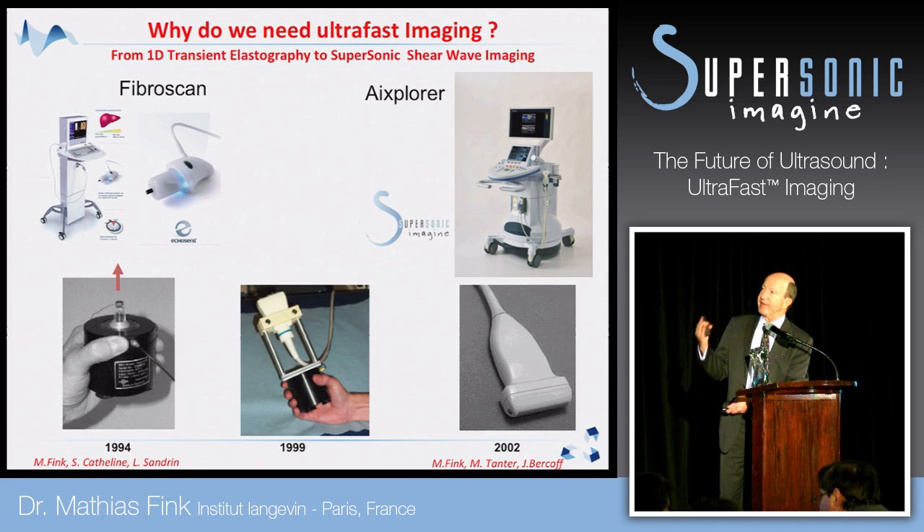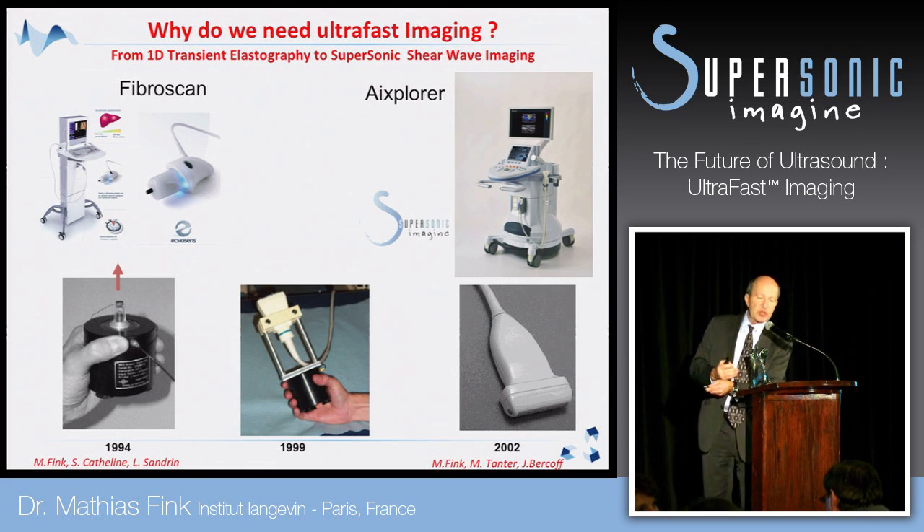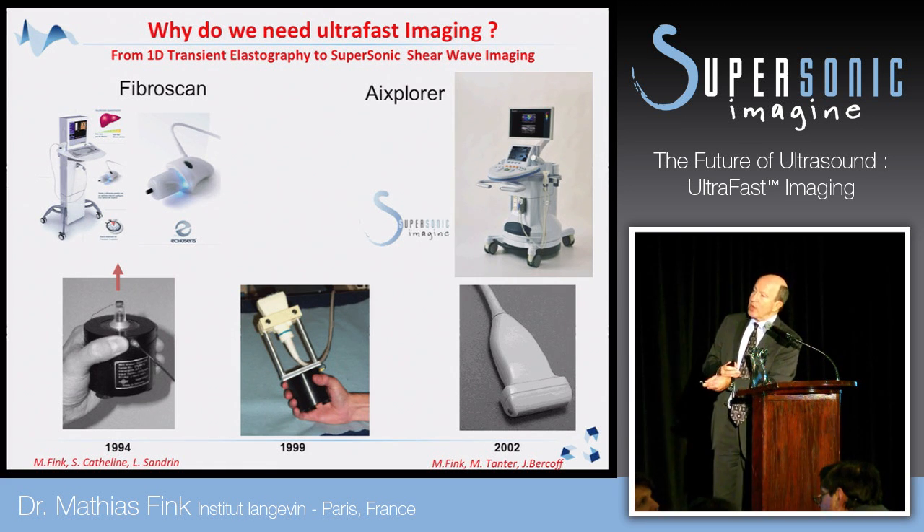In our lab in 1994 I had the idea to make a system to measure the elasticity of an organ. But it was not an imaging system — it was just to measure a global elasticity. We developed a vibrator that gives a punch in the body and we had only one transducer that could follow the shear wave. This gave rise to a company, Echosens, which produces the FibroScan that gives a global evaluation of elasticity. But we decided to go from that apparatus to an elasticity mapping apparatus, and for this we needed ultra-fast imaging to follow shear wave propagation in the whole organ.